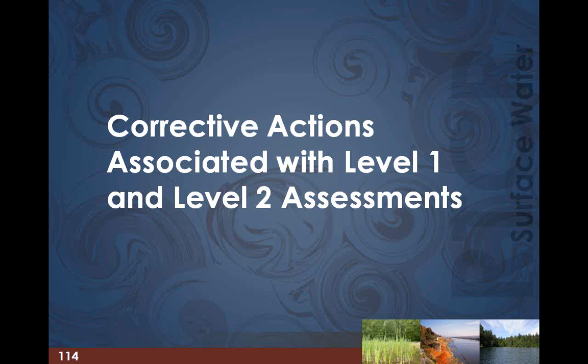A reminder that the treatment technique requirements are to conduct the assessment, fill out the assessment forms, and submit it to the state on time. Every single significant defect has at least one or more associated corrective actions. Those corrective actions in the form are either marked and shown to be complete, or there's a timetable with a proposed completion date. And so the system is not just on the hook for completing the assessments, but for completing the assessment, submitting the form, and completing the follow-up corrective action. And so now we're to the corrective action portion of this.